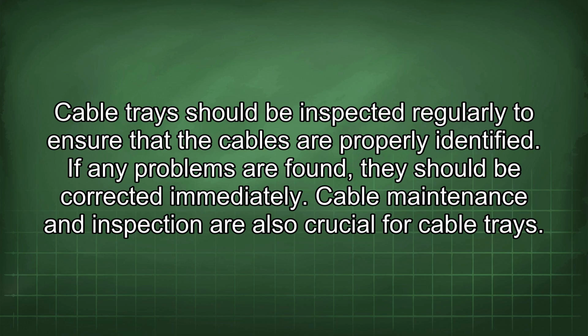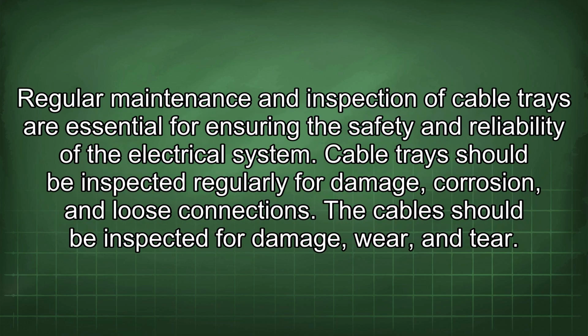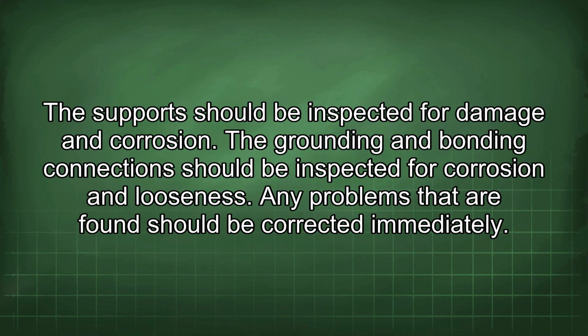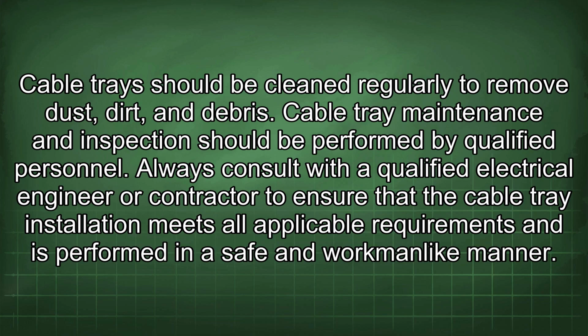Cable maintenance and inspection are also crucial for cable trays. Regular maintenance and inspection of cable trays are essential for ensuring the safety and reliability of the electrical system. Cable trays should be inspected regularly for damage, corrosion, and loose connections. The cables should be inspected for damage, wear, and tear. The supports should be inspected for damage and corrosion. The grounding and bonding connections should be inspected for corrosion and looseness. Any problems that are found should be corrected immediately. Cable trays should be cleaned regularly to remove dust, dirt, and debris. Cable tray maintenance and inspection should be performed by qualified personnel.